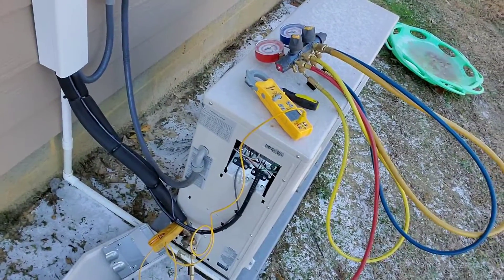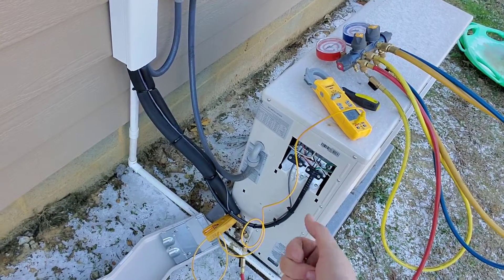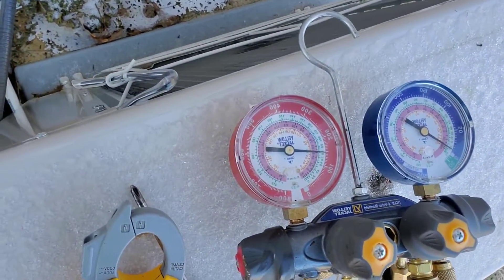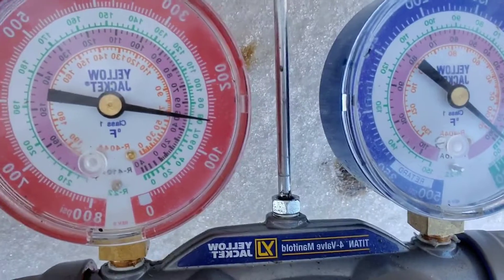A couple of things you need to look for: you need to get a temperature probe to clamp on the vapor line, you definitely need to measure the temperature going inside, and you definitely need to get some gauges. You've got to use your low-side gauge because most likely the high side is going to read upwards of 350 and just peg out there.